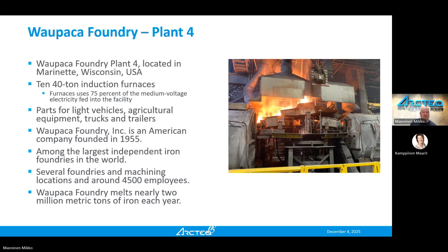In 2023, they made a huge upgrade with the safety. It was a massive retrofit installation and also a new build on the same plant, with the full setup of arc flash protection: arc flash detection, protection, and mitigation system in their medium voltage distribution. The main idea with this arc quenching device and mitigation system was also to have safer categories for the personal protective equipment, in this case from category 4 to category 1.